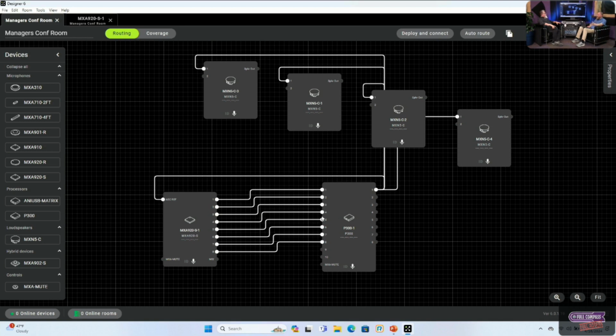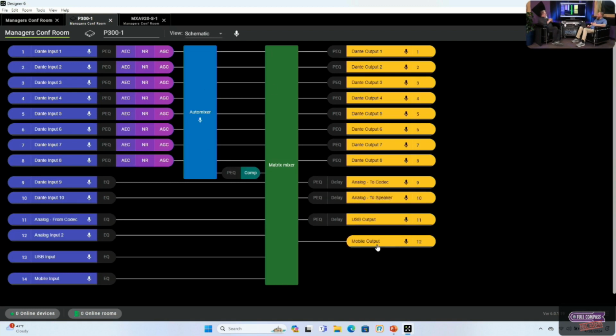Right. So the one thing that we didn't click on is our P300. This is our processor here. If I double click on this, we're going to see all of the processing that's within the P300. Because we were on those individual channels, it optimized. It knows I'm using a P300, so it turned off the echo cancellation in the microphone and is using the echo cancellation in the P300 for all of the processing, because it knows I'm probably in a more challenging environment. My first 8 channels here are my Dante inputs. Those are my lobes coming in. And then you'll see that we've got a parametric EQ, echo canceller, noise reduction, and automatic gain control. And then all of those individual lobes, or you can think of them as individual microphones, all go into the auto mixer.